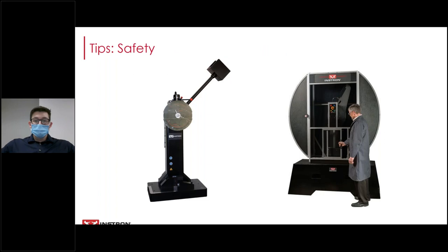So some details and factors to consider, and one of the most important in my opinion is safety. Pendulum impact testing involves fast-moving parts, and it can seriously hurt someone if you're not careful. So this is one of the reasons that Charpy manufacturers are moving on from manual test machines on the left here and evolving into an enclosed and motorized solution like the one on the right.